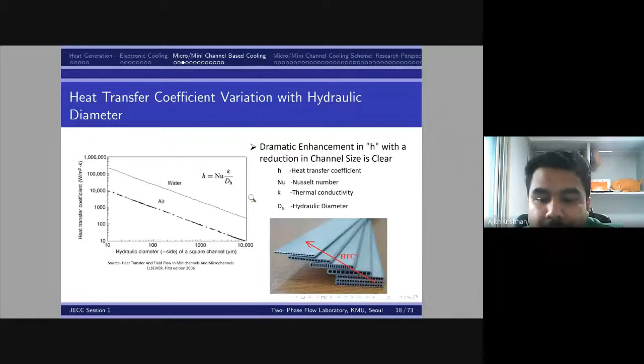So how is microchannel cooling adopted? There are two types of strategies: single phase cooling, and two phase cooling, which we call flow boiling. We have a processor from which heat needs to be removed, so we attach a heat sink or channel on top of the processor, inside which fluid flows. Here there is only single phase flow, because the heat dissipated from the processor is very low, so the fluid remains in one phase only inside the channel.